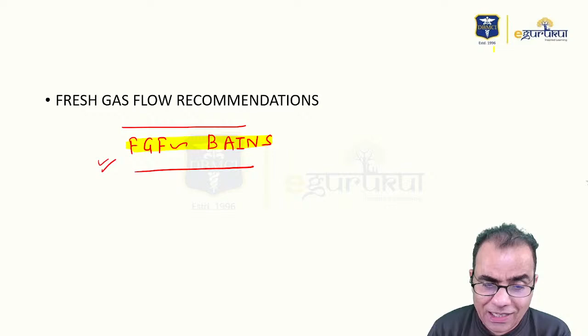So they say a closed circuit is actually just a theoretical phenomenon. Every closed circuit behaves like a semi-closed circuit because some gases are venting out into the atmosphere. The majority are closed, but some are venting out, so it is semi-closed. So, to avoid this confusion in terminologies, nowadays these closed and semi-closed circuits are only called circle systems. They say don't use these terminologies. Of course, the criterion is that the fresh gas flow requirement is very low, far lower than the minute volume, for both. So they will be classified under semi-closed, closed or circle system. The closed and semi-closed terminologies are now discouraged, and we have to use circle system.